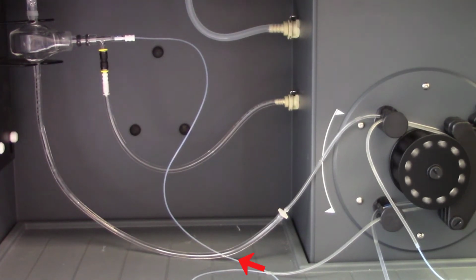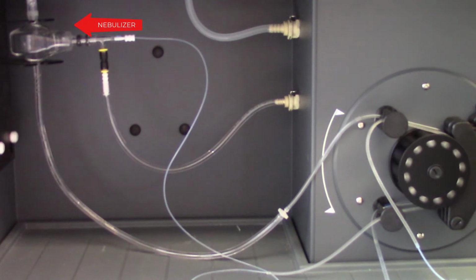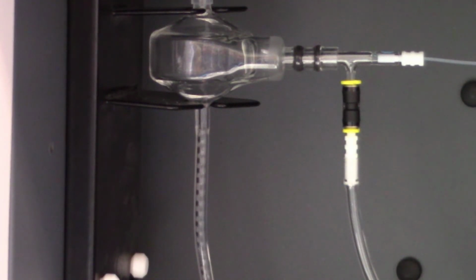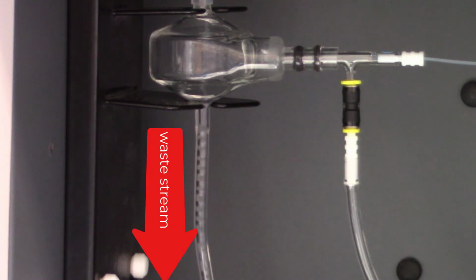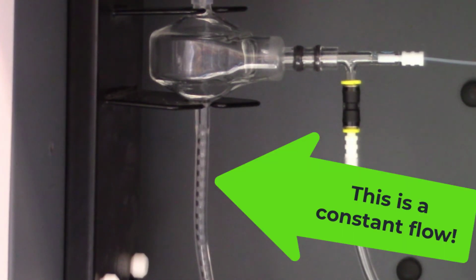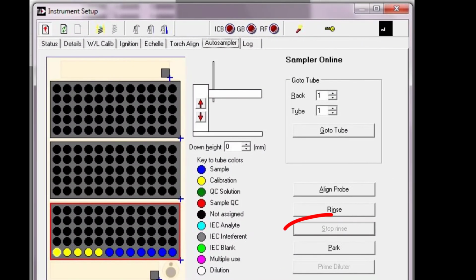Next, watch the solution flow into the ICP. It will gently spray the solution through the nebulizer. A very fine mist will move up toward the torch, which you will not be able to see, but the majority of the liquid will drip down into the waste container. Once you see a constant flow of solution, you know that your tubing is okay. In the software, click on Stop Rinse, and then the Pump Stop icon. Now exit out of the Instrument Setup window by clicking the red box in the upper right corner.